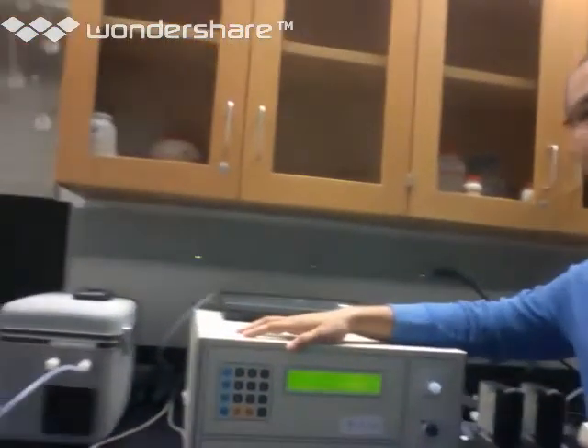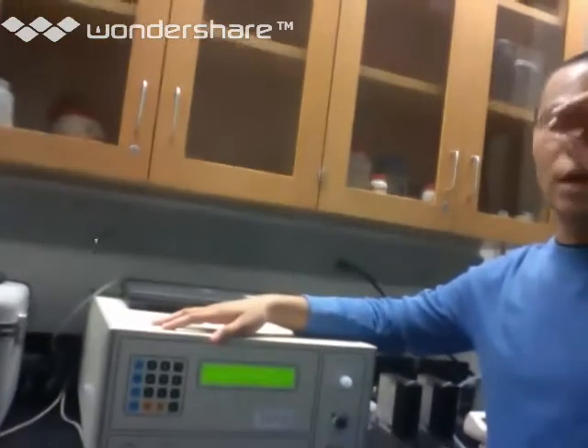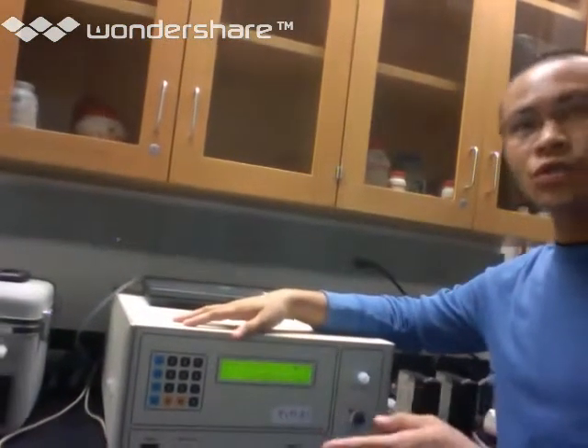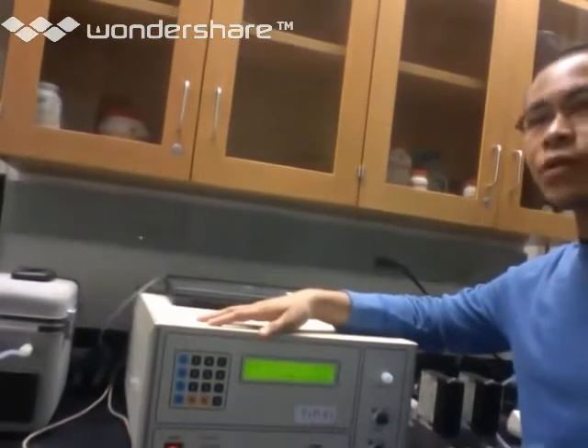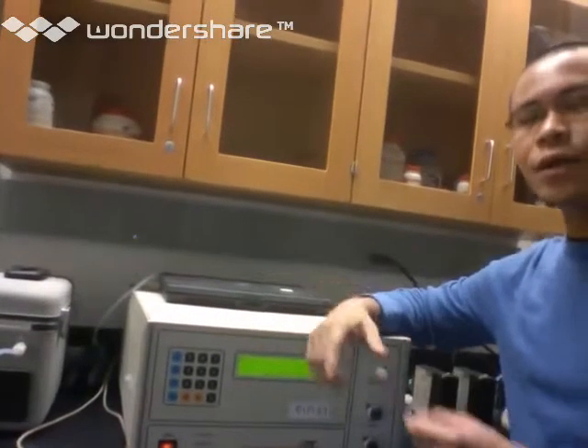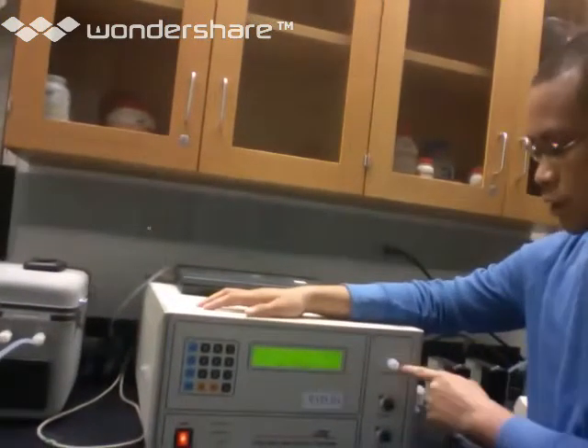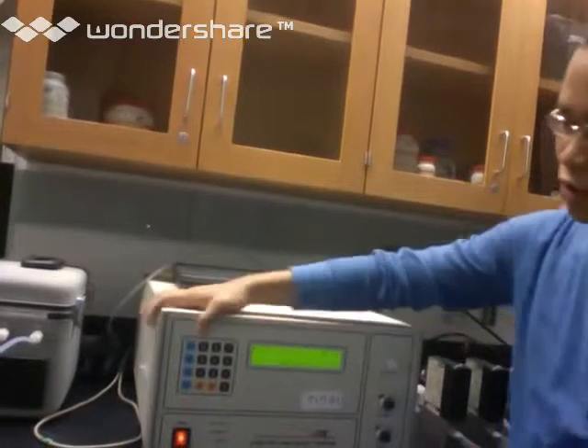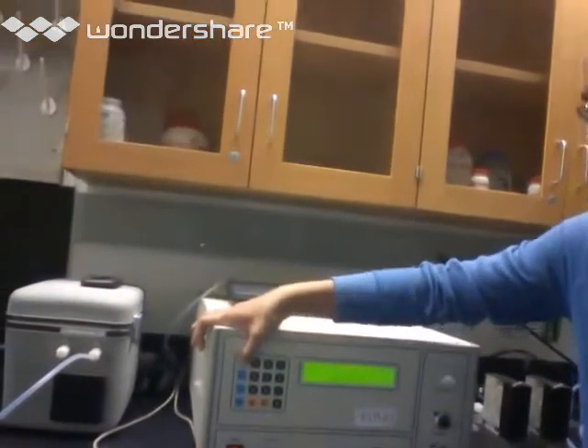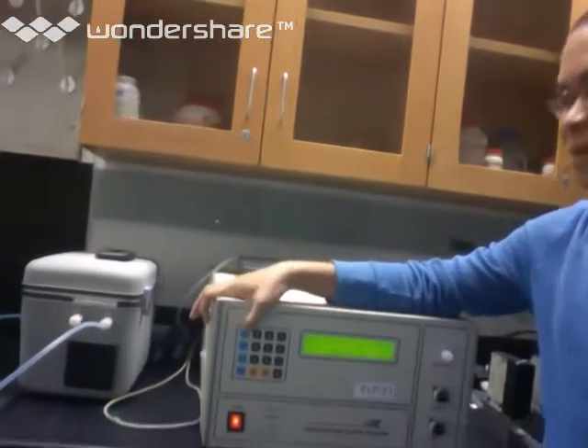So with the Tekrans, about once every month we like to do an external calibration, which essentially just means we use the external source. We pull out 10 microliters using that glass syringe in there, and we'll inject it into this here. So to start that, you always want to press escape a couple times to make sure you're on the main menu. If you can't escape anymore, you're on the main menu.